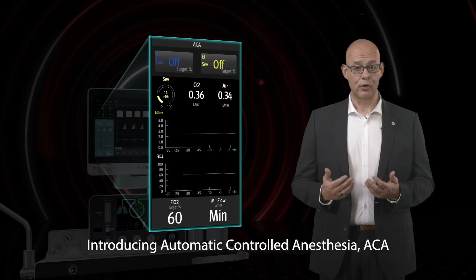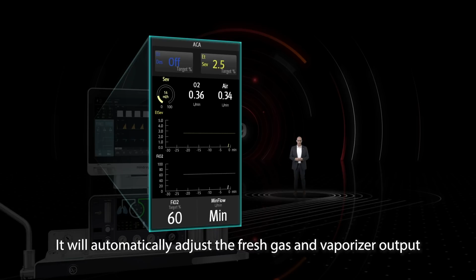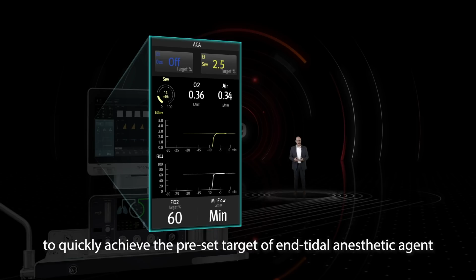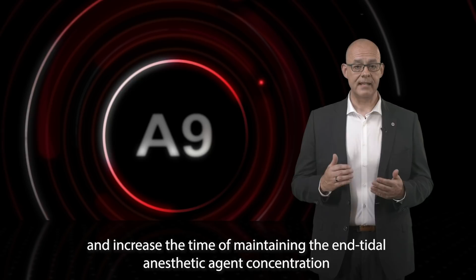Well, here is a feature to do just that. Introducing Automatic Controlled Anesthesia, ACA. It will automatically adjust the fresh gas and vaporizer output to quickly achieve the preset target of end-tidal anesthetic agent and inspiratory oxygen concentration. With this automatic control versus manual control, we can ensure a more stable level of anesthesia and increase the time of maintaining the end-tidal anesthetic agent concentration within the desired range by 30%.